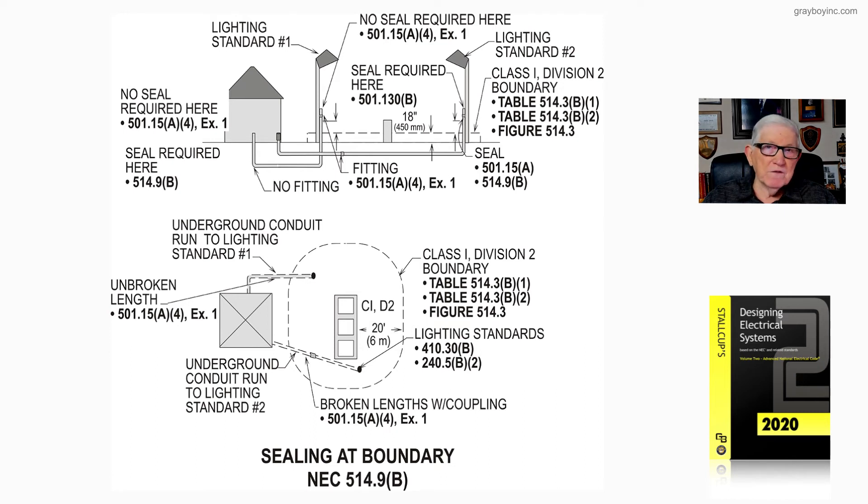Because you have broken lengths with couplings in the underground run, you're going to have to provide seals in accordance with 501.15(A)(4) Exception 1. At the top of the filling station, however, there's no coupling in that boundary — we have an unbroken length — so per 501.15(A)(4) Exception 1, no seal is needed.